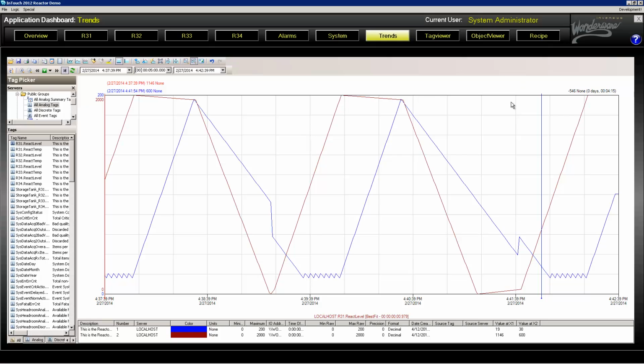Another trend tool that we've classically used has been an analysis client. Here's our full historian client embedded inside of this display. Again, it's a fantastic tool for data analysis, but when it comes to real-time process control, it has its weaknesses. There's only so many pens that you can embed inside of this before it starts to get somewhat noisy, and swapping out the tag groups that you're showing as you move from screen to screen can often be a laborious task as well.